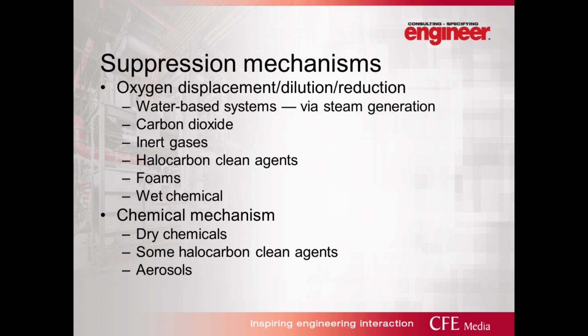Oxygen displacement and dilution reduction, I put these all together. Just about every suppression system works this way in some manner. Water-based systems do this via steam generation. As the water comes out of a sprinkler or a water mist system and interacts with the fire plume, it creates steam. And that steam actually displaces oxygen much more than you would expect. Carbon dioxide systems are completely based off of displacing oxygen to the point where there is not enough oxygen in the space to actually support combustion.